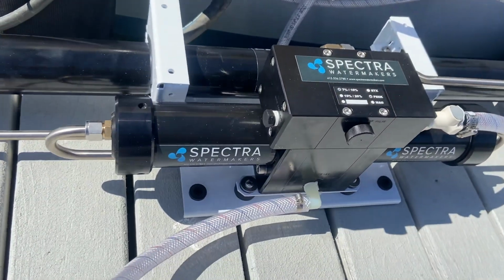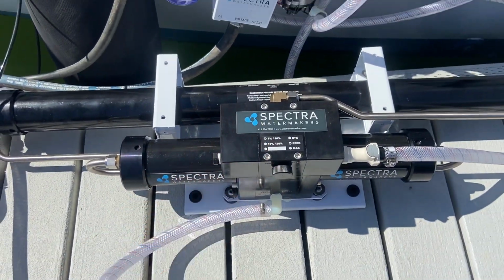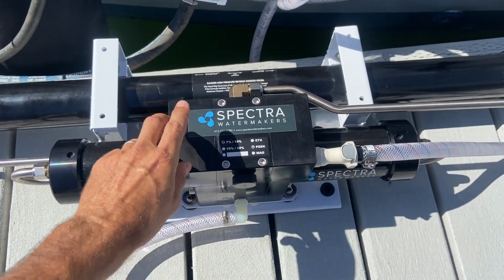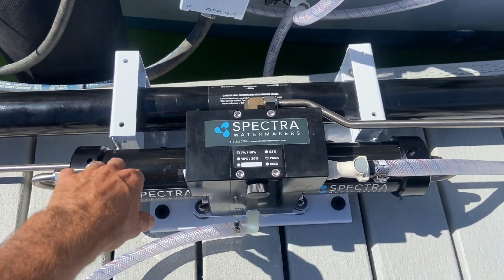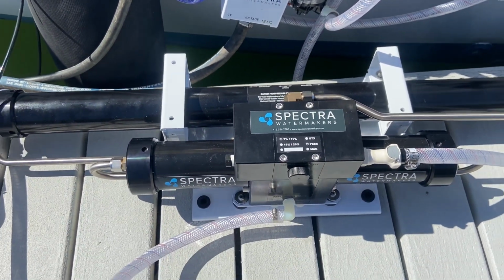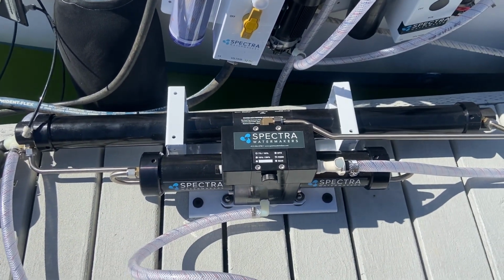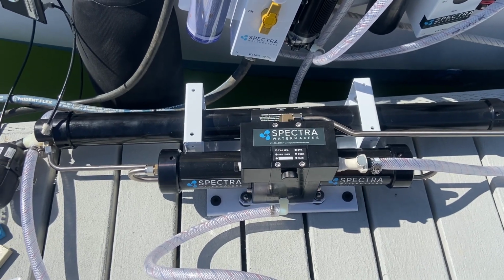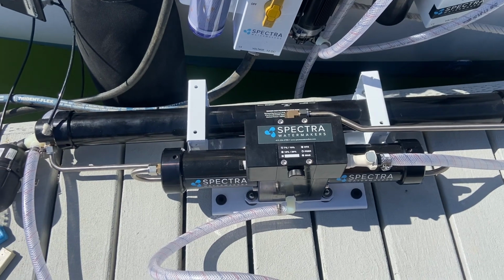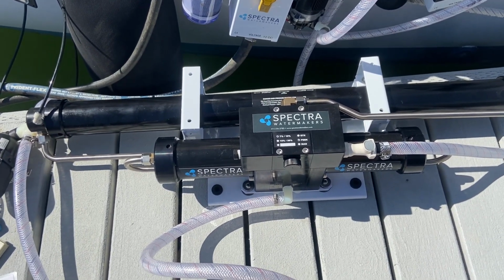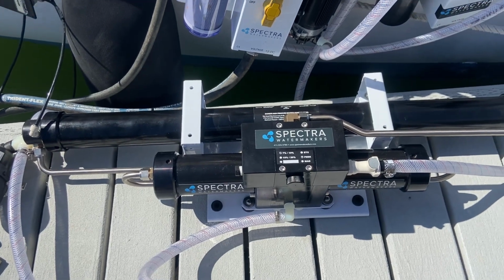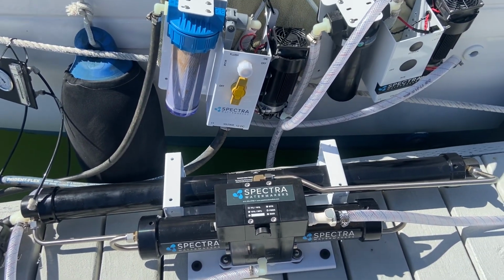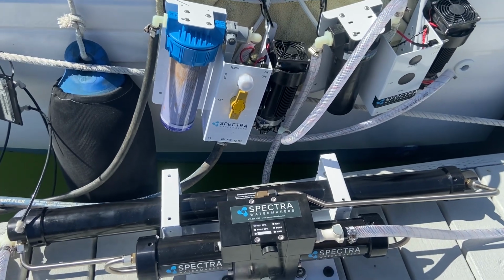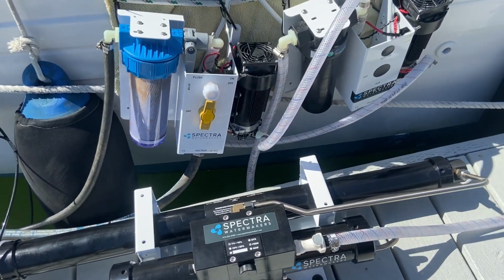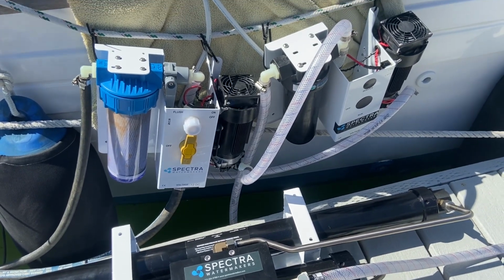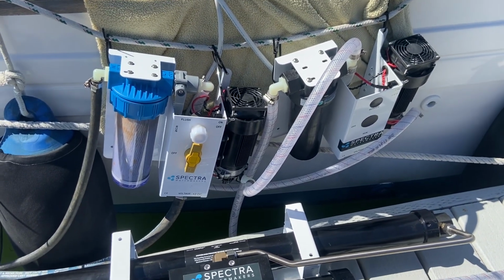Give a bit of an overview of the system. So this is the high pressure module, which consists of the Clark pump and the pressure vessel with a 40-inch membrane inside, all on an aluminum skid. This is essentially the same high pressure module on most of the Spectra line, the Catalina series, the Catalina 340Z, the Newport 400. The only difference is in how we feed it. Those systems all use a vane pump on an electric motor, which is great, but a vane pump will be destroyed in just a few minutes if it runs dry. So you have to have circuitry, a computerized system that'll shut down the system in case it runs dry.